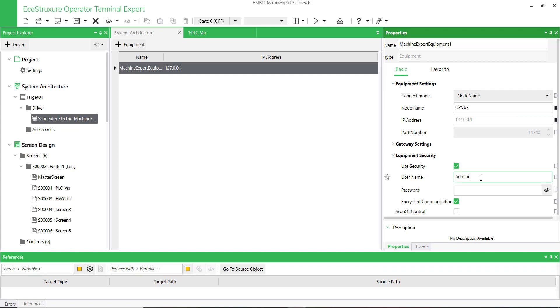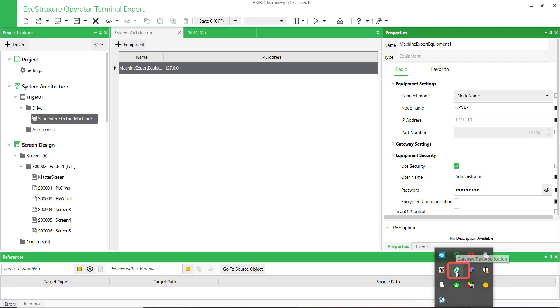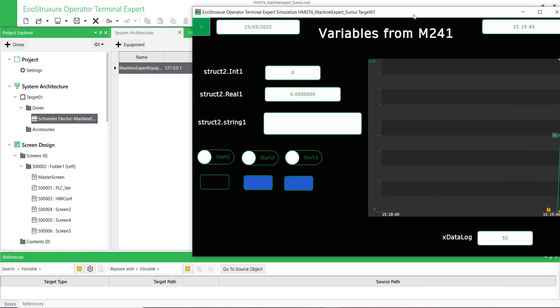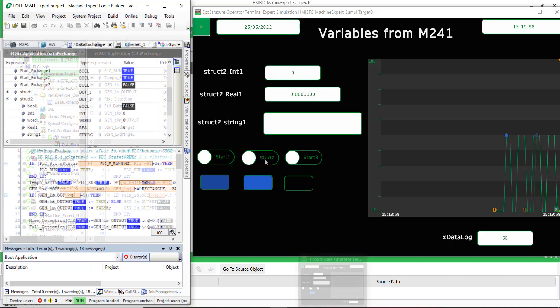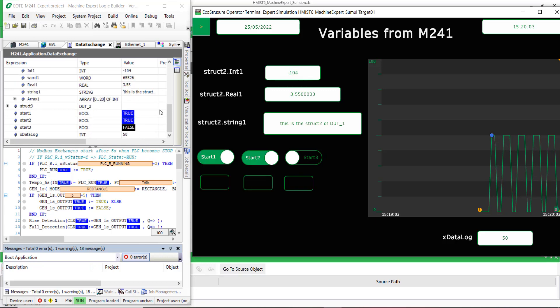Enter the PLC security information if required. Deactivate the encrypted communication — M241 and M251 do not support this function. Make sure that SoMachine Gateway is running fine. Run the HMI simulator. Display the simulator and Machine Expert connected to the PLC. You can see that the variables are exchanged properly between the HMI simulator and the PLC.